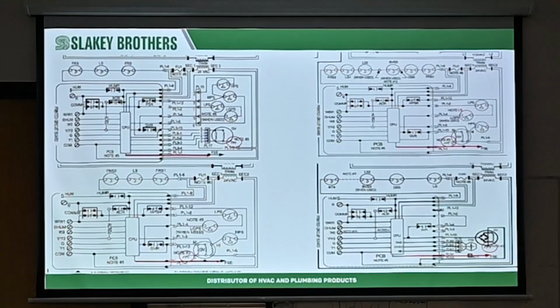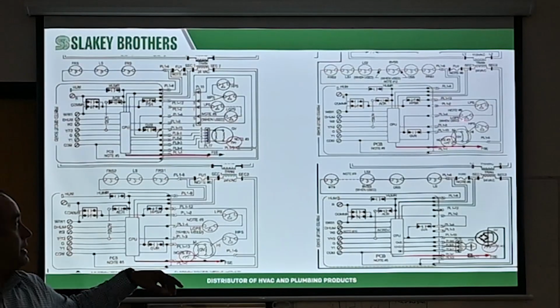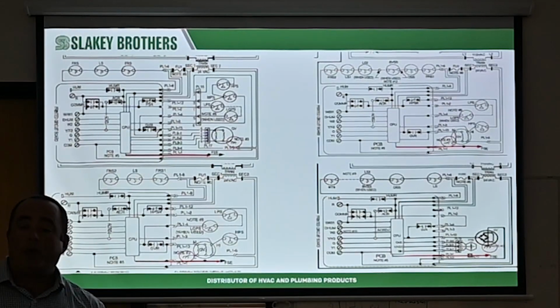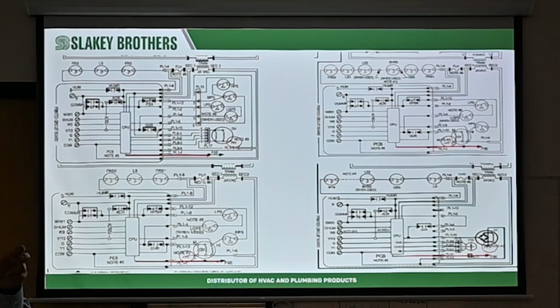This one here opens when pressure drops. This is a safety switch for the low gas pressure. When you do an LP kit, there's a little gas pressure thing that you put on there in the little T or with the little adapters, that if your propane pressure drops too low, it opens up. This symbol means that this switch opens with pressure drop. This switch is always open, and it means it closes when pressure drops. That's fine, it's supposed to close. When negative pressure is applied to this switch, it closes. And that's what those switches do.